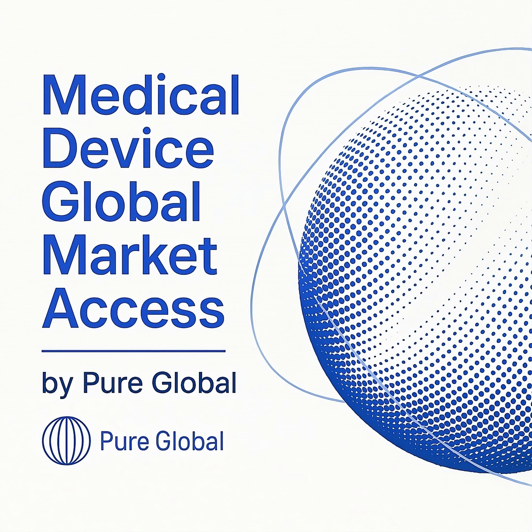Operationally, ISO 14155-2020 introduces several key changes. It formalizes the need for clinical quality management, requiring sponsors to implement systems and processes to ensure data integrity and compliance with the CIP. It also introduces the concept of risk-based monitoring. This allows sponsors to tailor the extent and nature of their monitoring activities based on a thorough risk assessment of the study, focusing resources on the most critical aspects. This is a move away from a one-size-fits-all approach to monitoring.